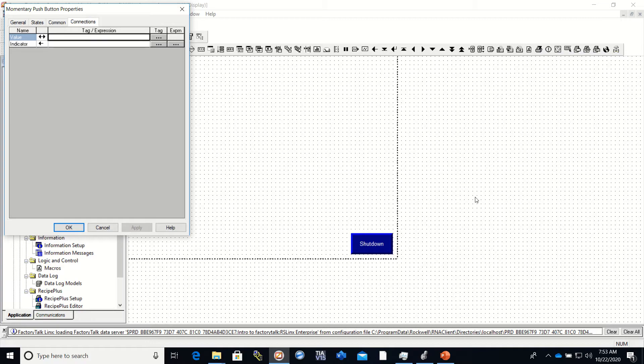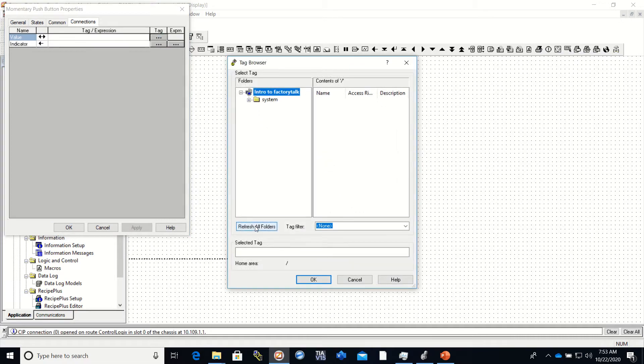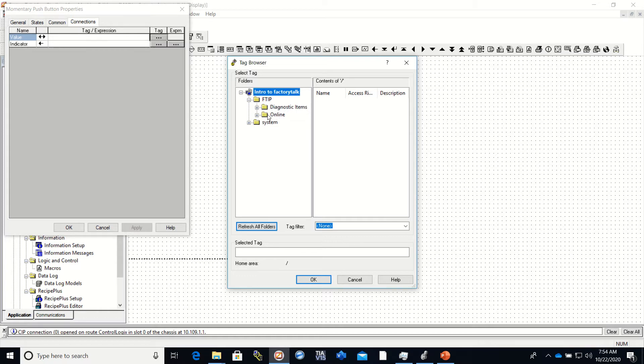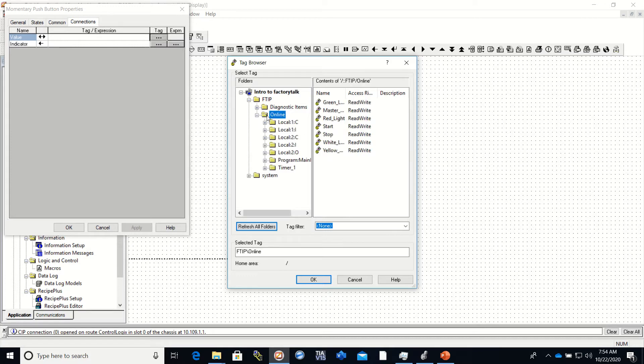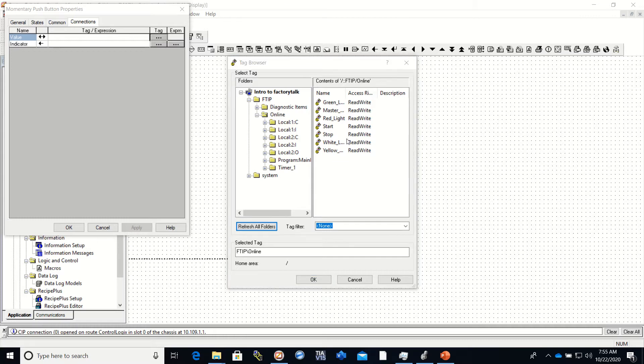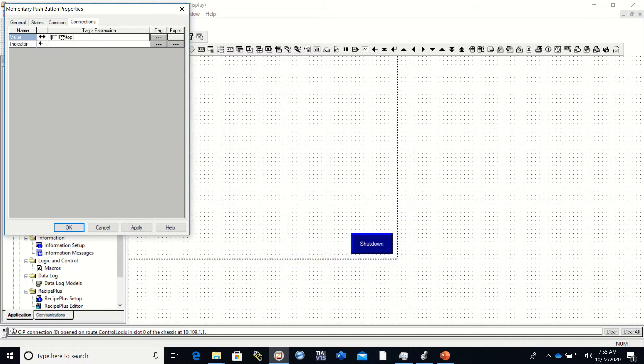Then we go to Connections — this is where we actually set up the connection. We've already set up the connection from Factory Talk View, but this is where we bring our tags over. I go to Tag and hit Refresh All Folders. You'll see right there the FTIP shortcut that I set up earlier. I click the plus sign, click on the folder, and you'll see it brought over all of my tags. I click on the stop tag and it puts it in right down here.